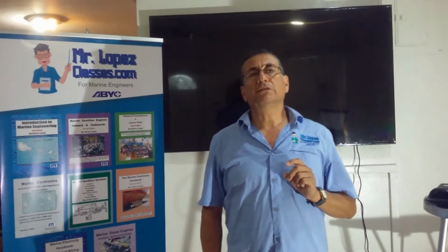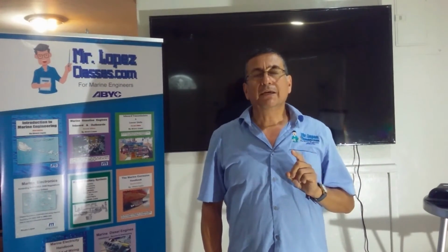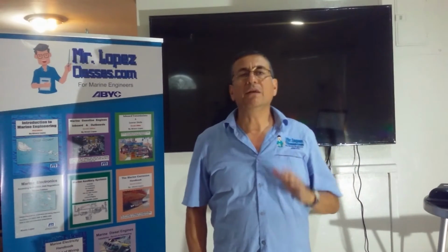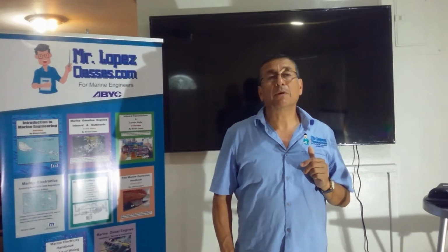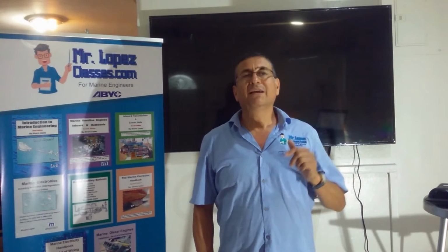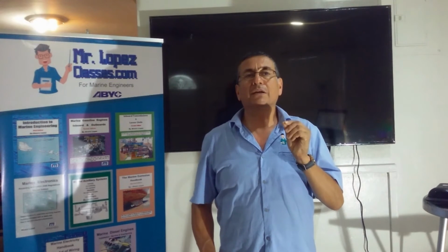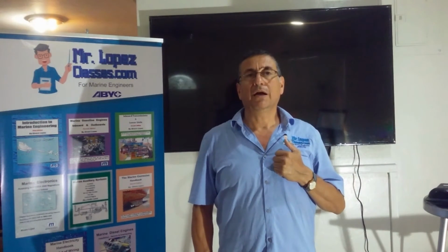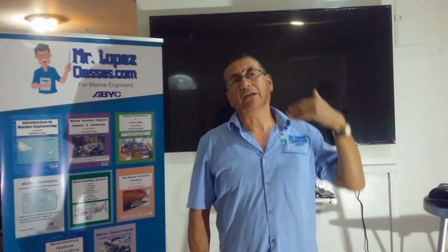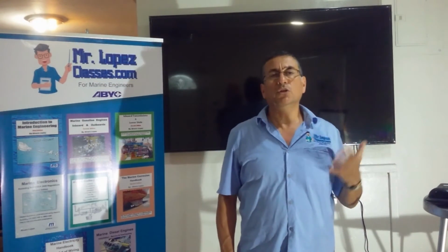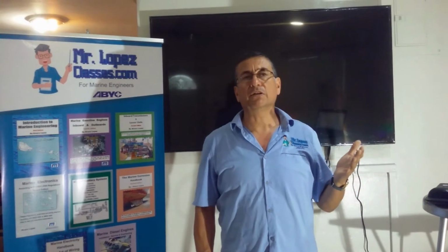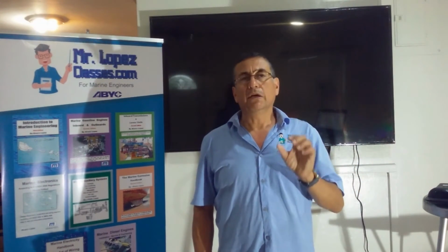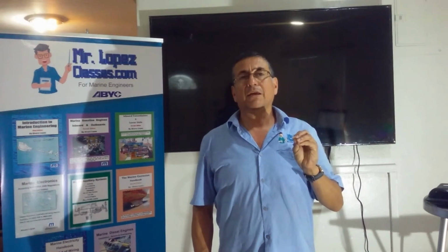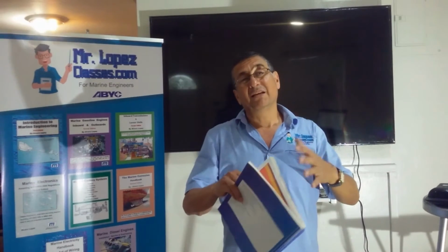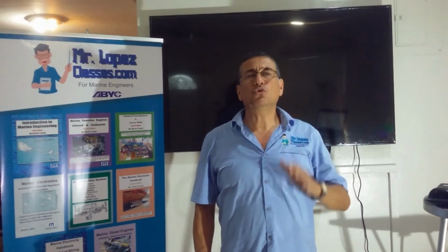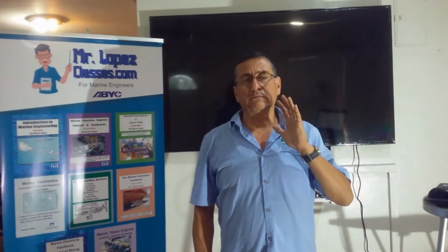Another important recommendation is in relation to marine inverters. Always install marine inverters. Why? Because marine inverters have the neutral and the ground connected together internally at the source of the power, and you don't have any problem after that in the boat. Industrial or residential inverters don't have the neutral and the ground connected internally, and you probably need to connect them externally, and that's confusing. Always use marine inverters.